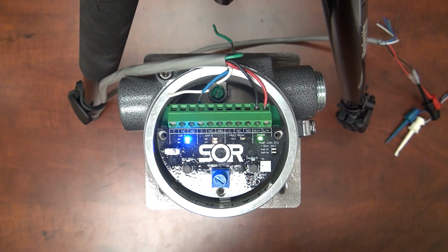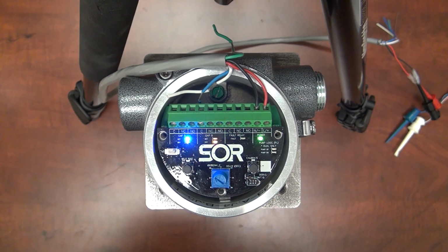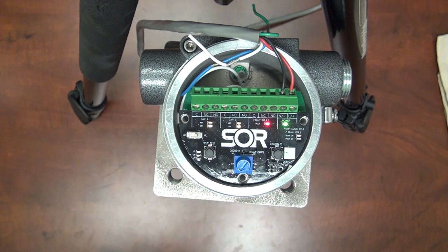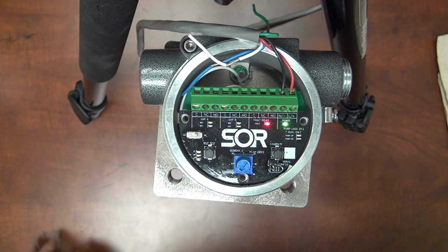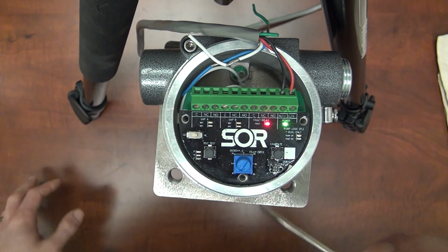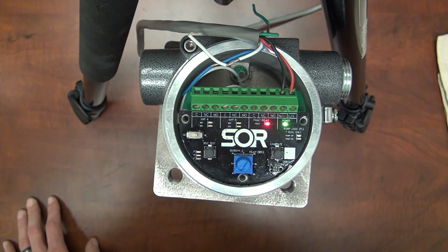This will be seen by the gap A-B wet and dry LEDs flashing rapidly, but their speed and frequency will decrease as it gets towards the end of the calibration. As the calibration is finishing up, we will see them flash rapidly 5 times, like what's being seen here, and then they'll flash on and off for 1 second, indicating that the sensorless calibration is now complete. However, we still see that there is a fault LED on, with the 2 dry LEDs flashing. This is an indication that a new dry calibration is required.